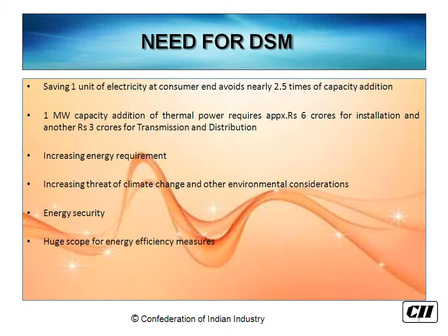This slide shows the real financial benefit of demand side management. If I can save 1 megawatt of power, that megawatt requires about 6 crores as installation cost, as capital cost for power generation, and another 3 to 4 crores for transmission and distribution. And here I am speaking only of capital expenses. So if I can save 1 megawatt of power, I can save about 9 to 10 crores of investment in the power sector. This is the real benefit of demand side management.